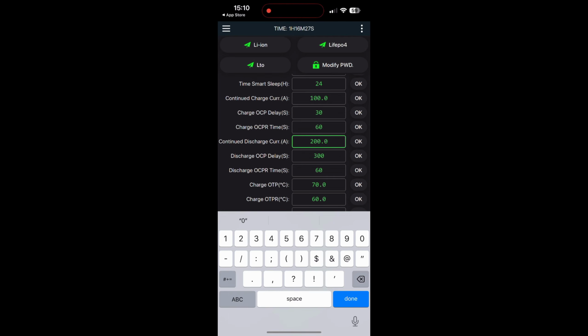And then after 60 seconds, it'll turn back on and allow charge current to start coming back. Same thing with the discharge current. Again, these are 200 amp hour cells. You can choose how you want to discharge them. They'll take 200 amps every day of the week, so I'm happy to leave that at 200, but you can change that if you want. You might have a device that can't handle more than X number of amps, so you can change that there. Same thing: how long do you want it to sustain that maximum before the BMS detects it?